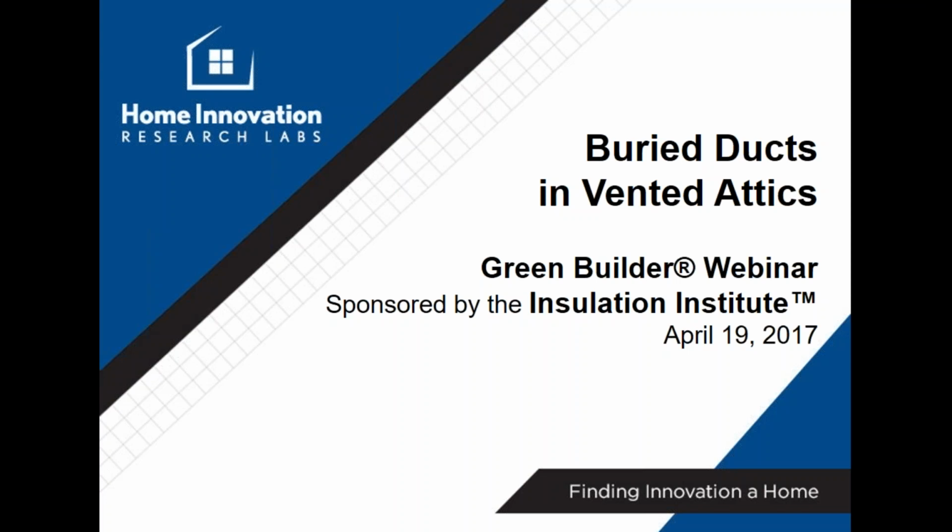Now, the 2018 IECC laid out a prescriptive approach for using buried ducts with fibrous insulation in vented attics for all climate zones. This new path will allow builders to get much of the energy efficiency benefits of an unvented attic with closed cell spray foam by instead doing a traditional vented attic with the ducts buried in fibrous insulation. Some of the research used to support this code change was performed by our guest today, Dave Mallay.